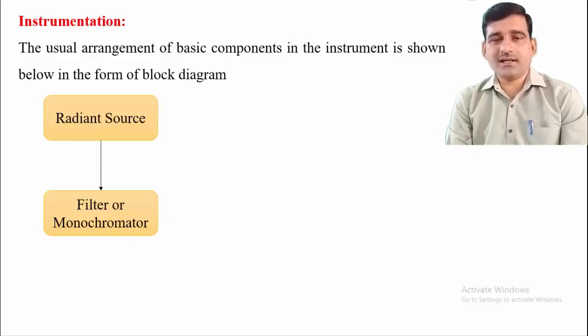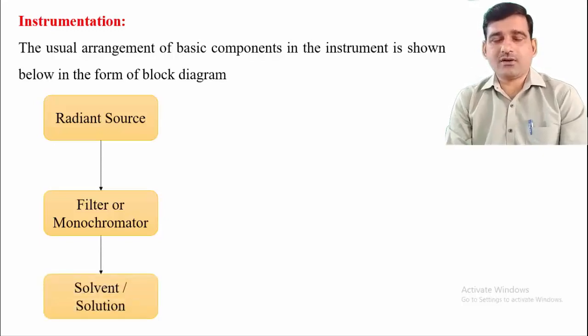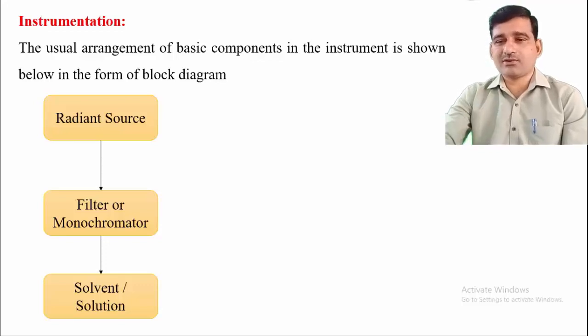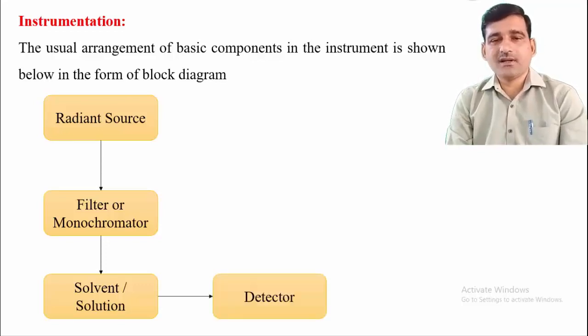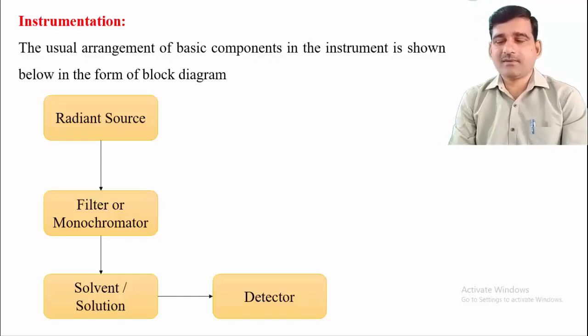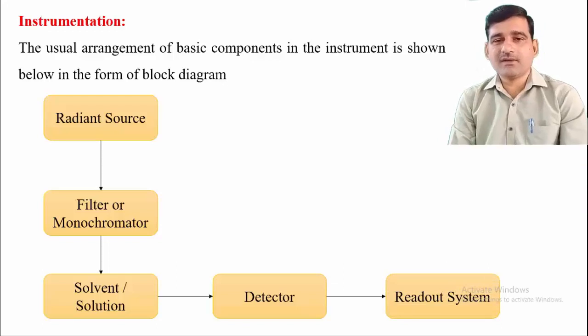Because the radiation source contains polychromatic light, that light must be converted into monochromatic light, and for that we require filters or monochromators. Then this monochromatic light travels through the sample solution or solvent where the actual absorption takes place. The detector then detects how much light is absorbed by the sample and how much light is transmitted.